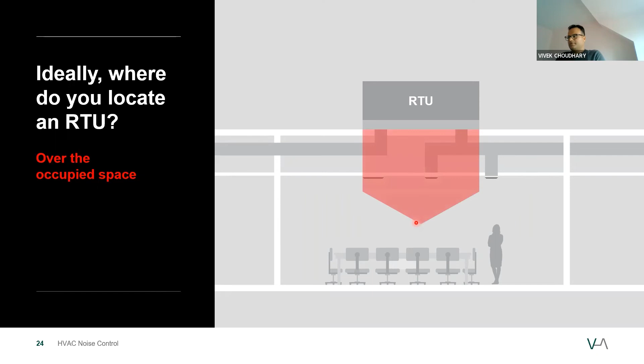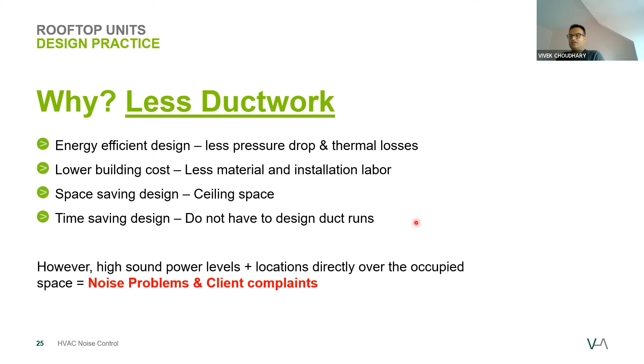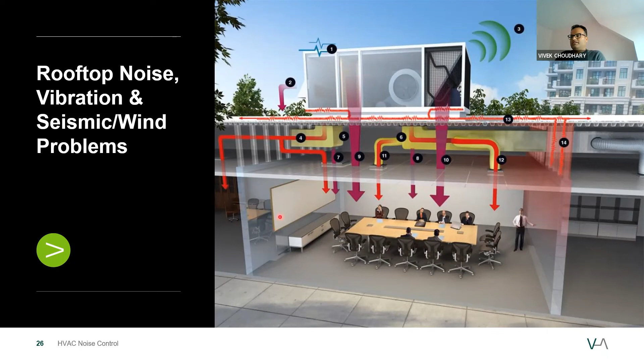There are some benefits to doing that: energy-efficient design, lower building costs, space-saving design, and time-saving design. But the problem will be noise issues and client complaints. If we have a rooftop unit located right above a meeting room, there can be 14 different noise paths that noise can travel through into the occupied space.